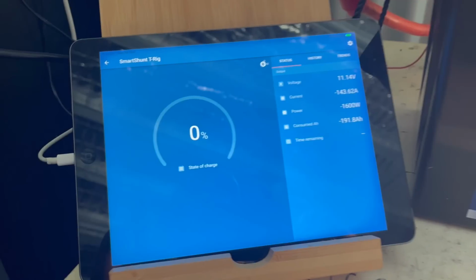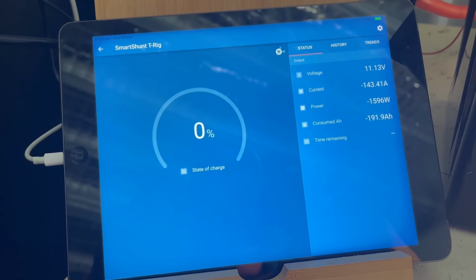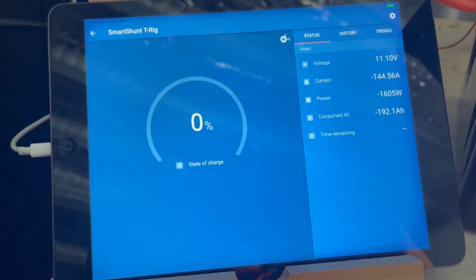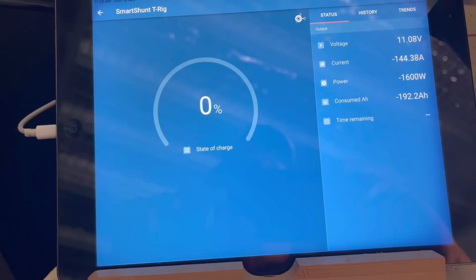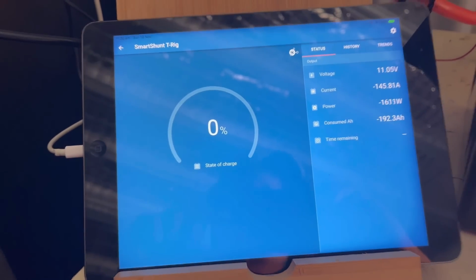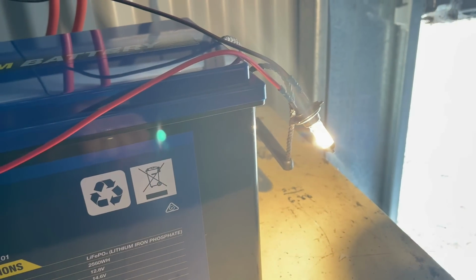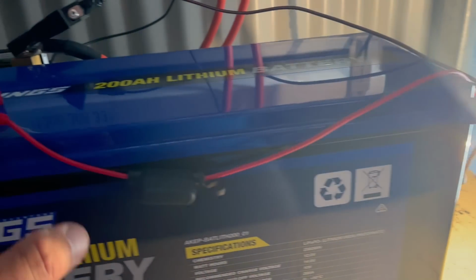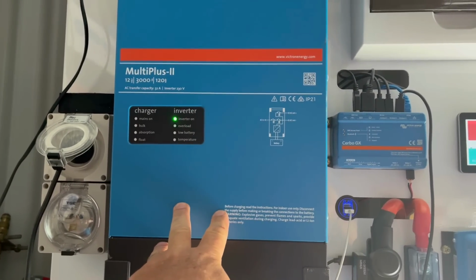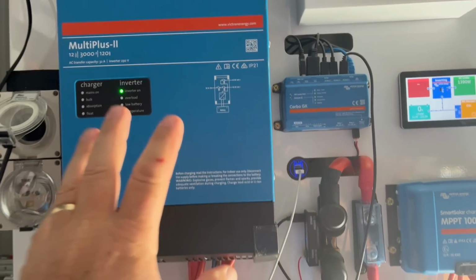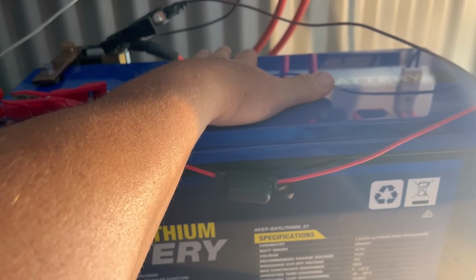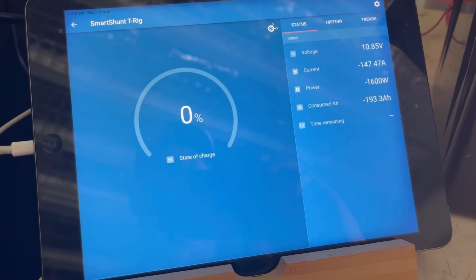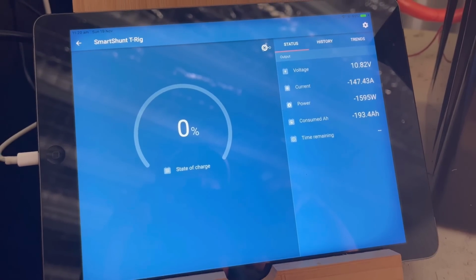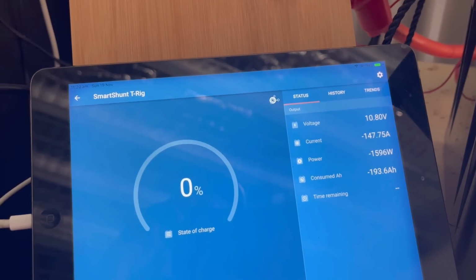Okay, so we've come down now to 11.13 volts at 192 amp hours consumed. What I've done is I've put my little H7 globe or whatever it is on the side here straight onto the shunt and the positive terminal, because I'm assuming what's going to happen is the inverter is going to cut out at 9.3 volts. The BMS will continue to operate, and then we'll drain the last little bit out of this battery and try and get 200 out of it. So 10.82, it will start dropping off very quickly now.